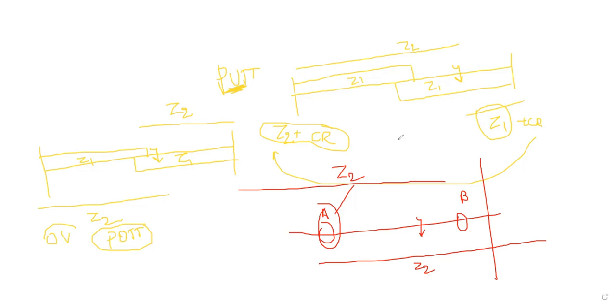But in your case, you told about overlapping. Maybe the 80% of the fault is a zone 1 fault. The relay, instead of detecting 80% of the fault, may detect it as 90% of the fault. Instead of a zone 1 fault, the relay detects a zone 2 fault. By mistake, it is overreached. Because of that, the zone 1 fault is overreached. It was supposed to be detected as a zone 1 fault, but by mistake the relay detected it as zone 2. So it is giving a maloperation. It's going for what is called the overreach.